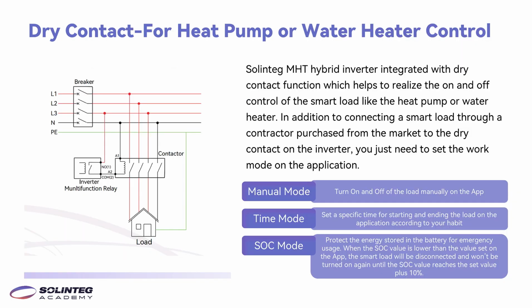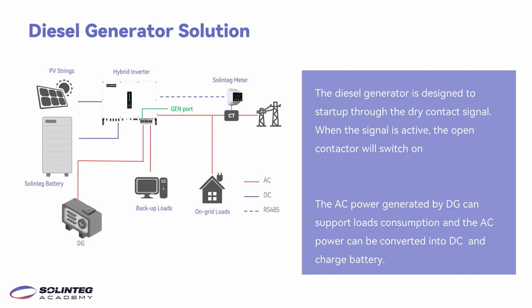Our inverter is integrated with the dry contactor function, which can realize control of the smart loads such as the heat pump and the water heater. There are generally 3 modes to control the smart loads: the manual mode, the time mode, and the SOC mode. This page shows our diesel generator solutions. We control it through the dry contactor signal. When the signal is active, we close the contactor and the generator will switch on.